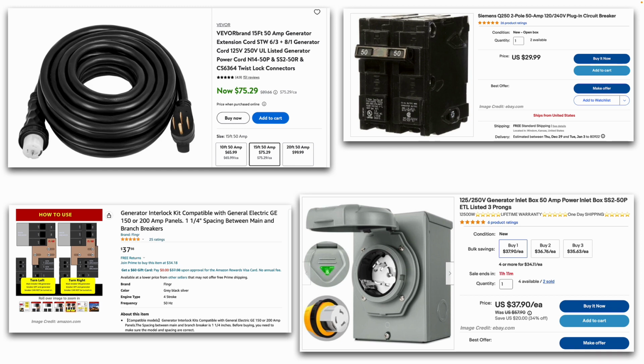Again, this one is 6-gauge wire. And even though it's 6-3, what you have inside there is 4 conductors. So you've got your neutral, your 2 hots, and your ground. And again, this one's good for 250 volts, 50 amps. So you want to make sure everything has a proper amp rating, right? So if we know our generator is capable of putting out almost 50 amps, then of course we need to make sure our power inlet box is rated for 50 amps. The 2-pole 50 amp breaker, again, rated for 50 amps. The power cord, rated for 50 amps. You get the idea.